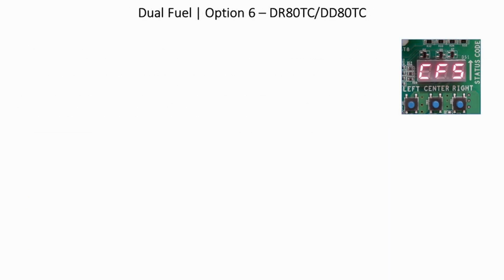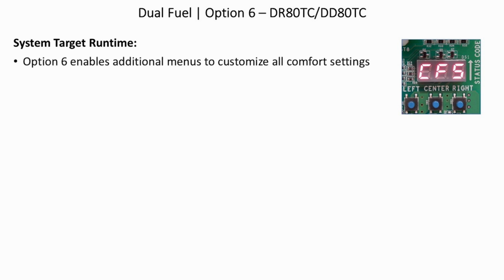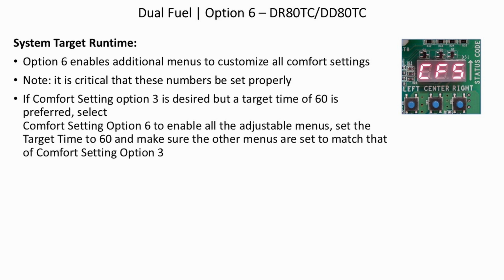Dual fuel, option 6. System target runtime. Option 6 enables additional menus to customize all comfort settings. Note, it is critical that these numbers be set properly. If comfort settings option 3 is desired, but a target time of 60 is preferred, select comfort settings option 6 to enable all the adjustable menus, set the target time to 60, and make sure the other menus are set to match that of comfort setting option 3.